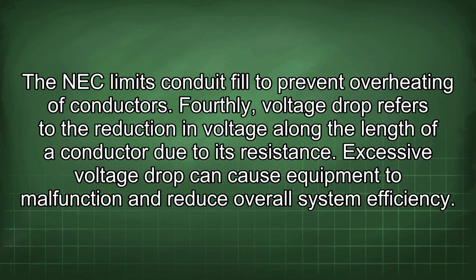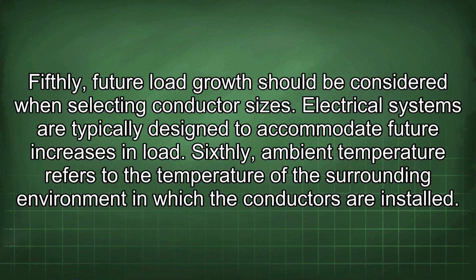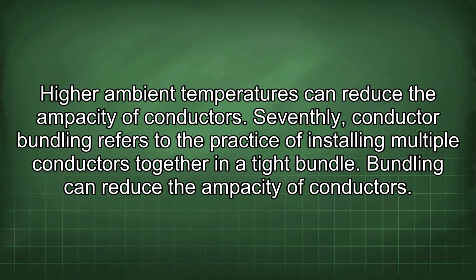Fourthly, voltage drop refers to the reduction in voltage along the length of a conductor due to its resistance. Excessive voltage drop can cause equipment to malfunction and reduce overall system efficiency. Fifthly, future load growth should be considered when selecting conductor sizes. Electrical systems are typically designed to accommodate future increases in load. Sixthly, ambient temperature refers to the temperature of the surrounding environment in which the conductors are installed. Higher ambient temperatures can reduce the ampacity of conductors.